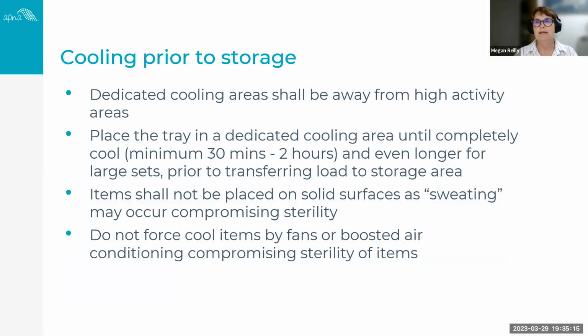Cooling: you need a dedicated area away from high activity within your reprocessing area so the items can cool, and they should come to a complete cool. That can be a minimum of 30 minutes, and with some items as long as 2 hours or even longer. But for the purpose of office-based practice, we do tend to use small sets of instruments, individual instruments, so they will dry quicker. But they need to be dried and cooled prior to transferring to your storage area.